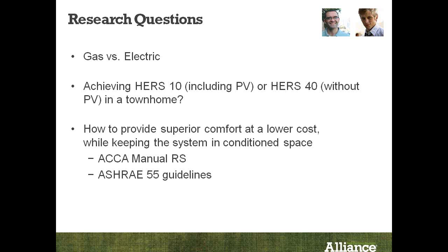So what we're likely to see is that the traditional system does a lot of short cycling. That's one thing that we would expect to see. And with short cycling, we might see increased humidity. Mm-hmm. Although in Denver there isn't a lot of humidity, right? But it'll be great to see this when we're done. We'll probably plot this on a psychrometric chart and do the actual ASHRAE 55 comparison.